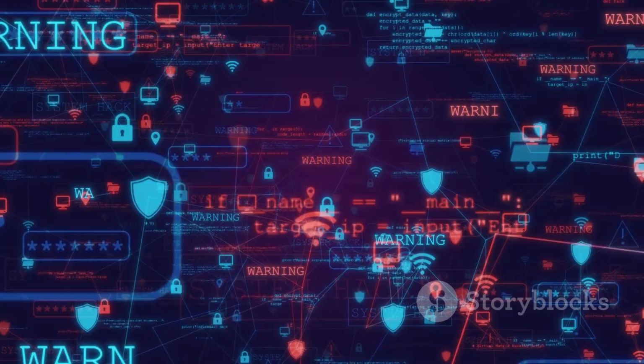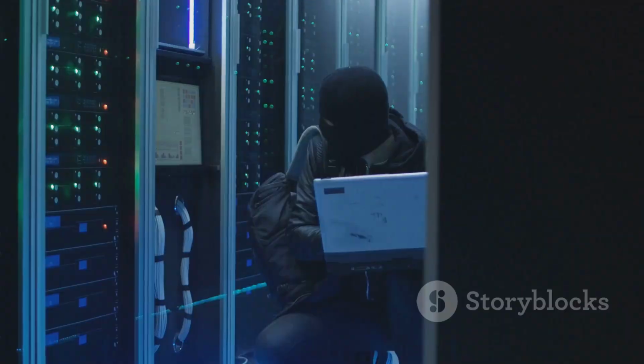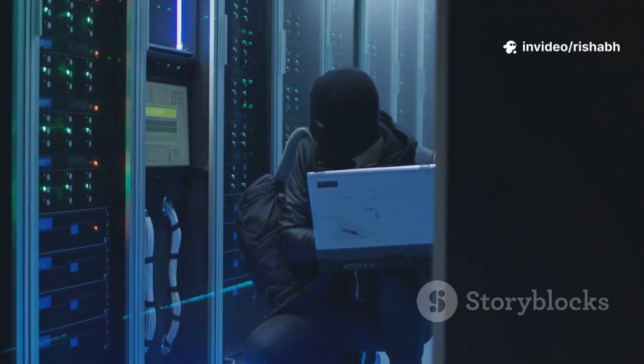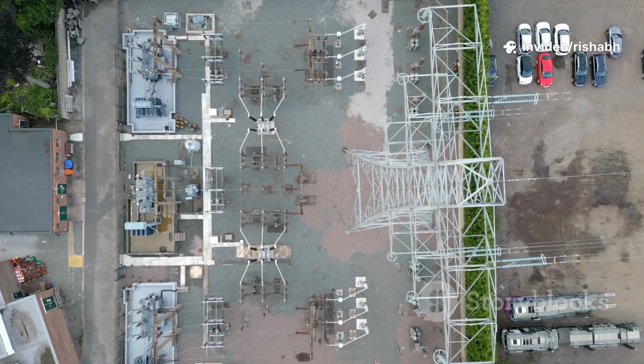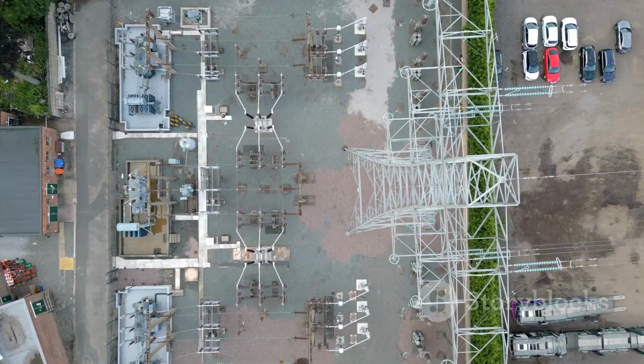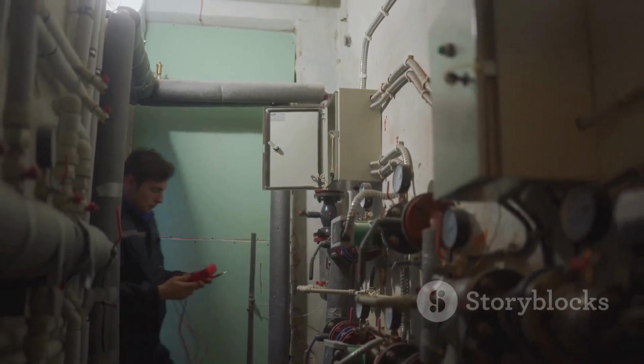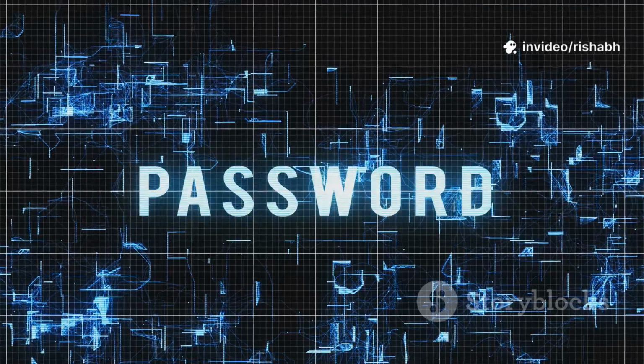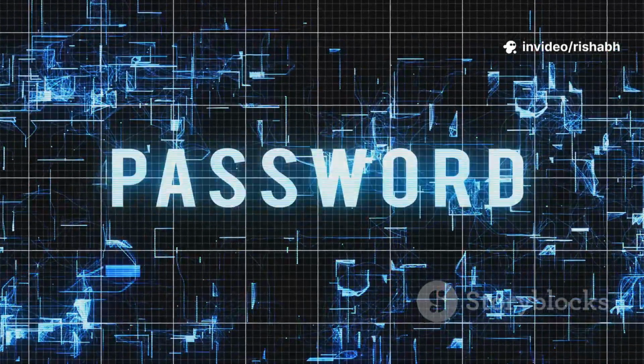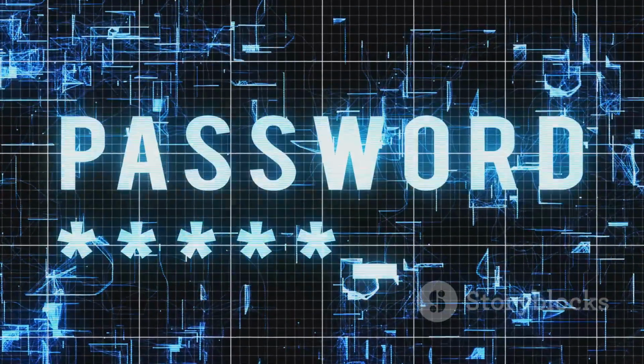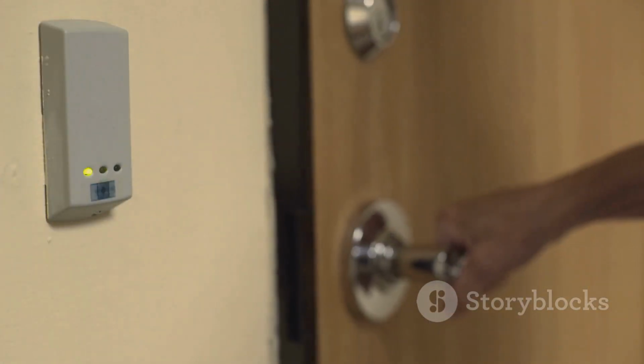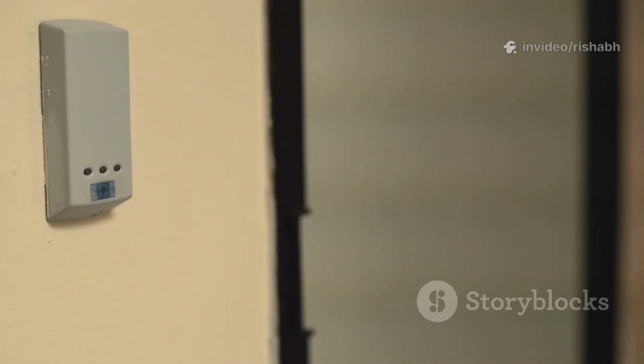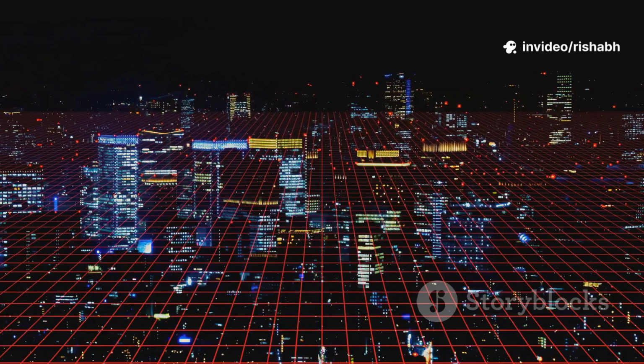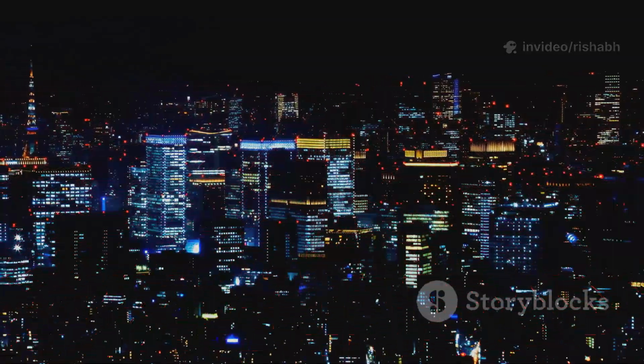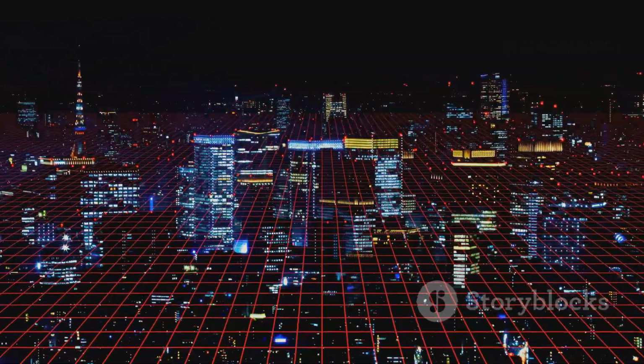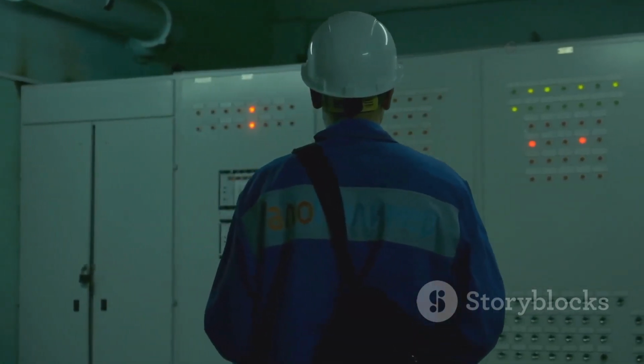This connectivity, however, brings a new challenge: cybersecurity. Anything connected to a network can be a target for cyber attacks. A malicious actor gaining control of a transformer protection relay could cause immense disruption and damage. GE has built the Multilin 845 with this threat in mind. It incorporates robust cybersecurity features such as password controls, user access logs, and encrypted communications. This creates a digital fortress around the relay's brain, ensuring that only authorized personnel can access its settings or issue commands. In an age where our critical infrastructure is increasingly digital, this cyber shield is just as important as the electrical protection.